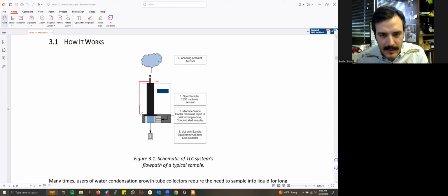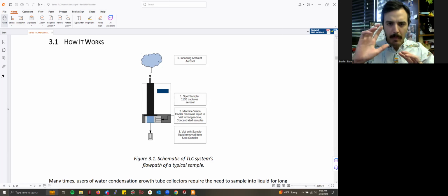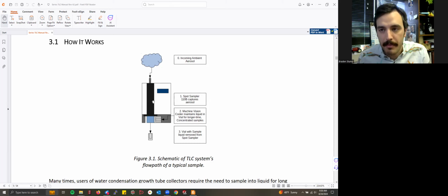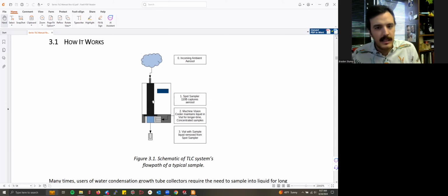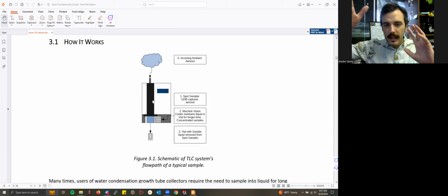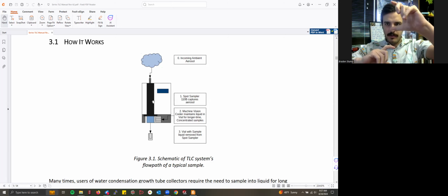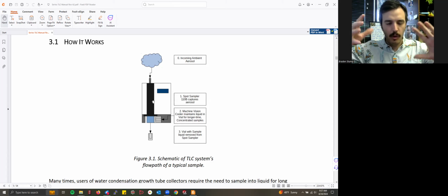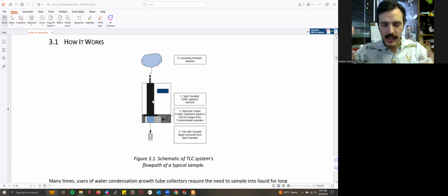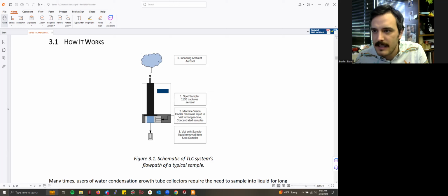So an instrument like the spot sampler, typically sampling into a liquid vial, we don't have the ability to dynamically control moderator temperature or temperature of your sampling vial over the course of a sample for, say, 8 hours, unless you're manually modifying it. The problem with that is, as we've discussed plenty of times, you can see a lot of change in liquid level due to particle concentration changing during your sample, and also just the thermodynamic balance between your moderator temperature, so your outcoming total water vapor in the flow based off of the exiting dew point that you're setting with your moderator, as well as the temperature of your sample, because the temperature of that liquid versus the amount of water vapor and what temperature it's coming out is going to affect evaporation or condensation into your liquid vial.